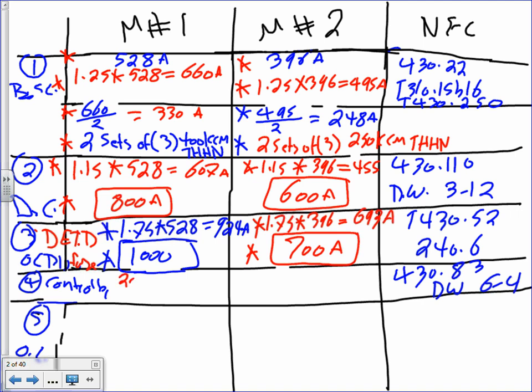The first one is 200 horsepower at 208. And the second one is 150 horsepower at 208. Remember, all of them are three phase, 208 volt. If you go to 6-4, please make sure you know how to use that one when you size your NEMAs. 6-4 looks like this. And when you have 6-4, there's a single phase and three phase. Obviously, we are looking at the three phase here. For 200 horsepower under 208, it says 208 and 200. You need what number?